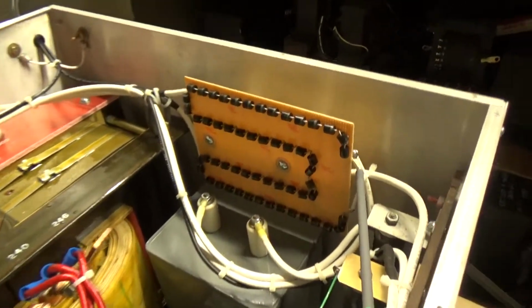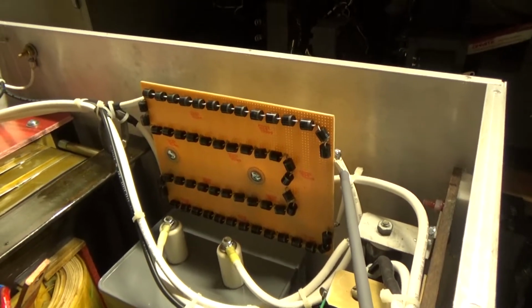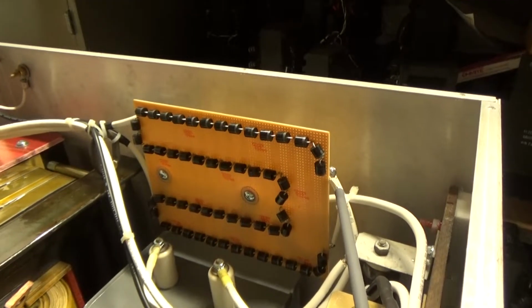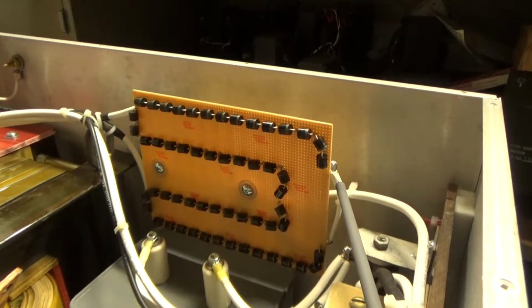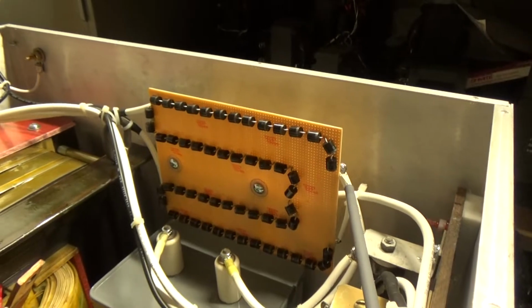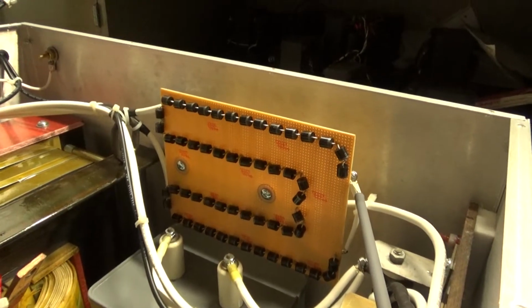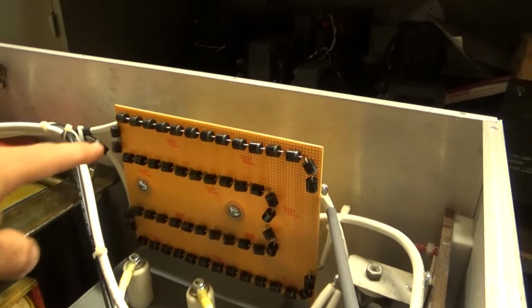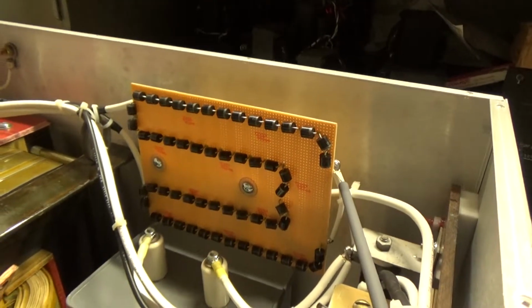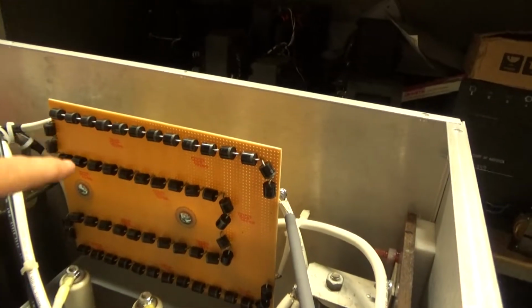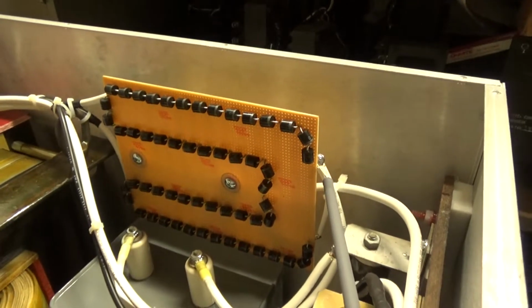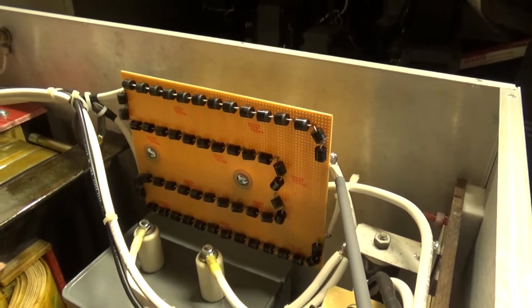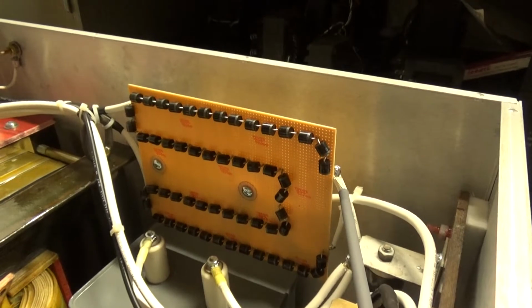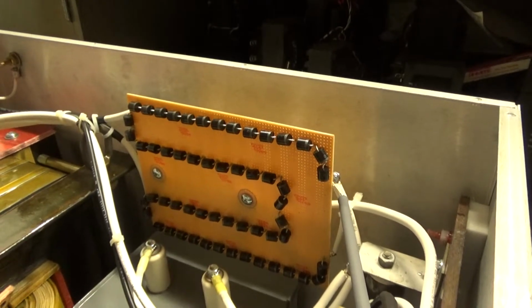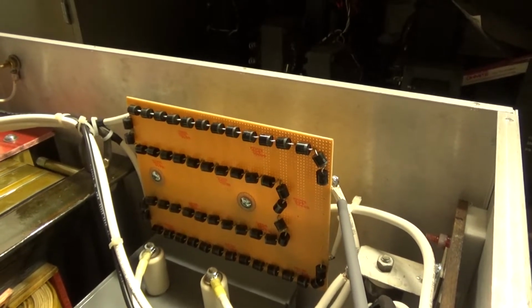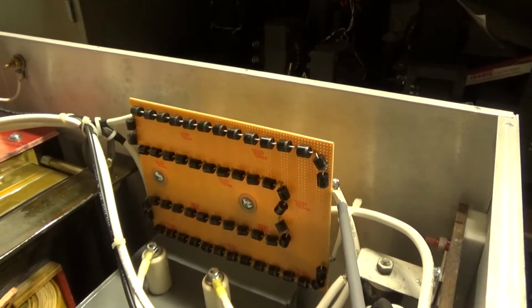Here's the rectifier board that I made. I ended up taking the board and high-potting it before I replaced the diodes to see what the voltage breakdown rating would be between each string. It was over 20 kV, so I always want to be sure before I do anything. I always check everything—I always want overkill to everything, so if something weird happens, I want it to survive.